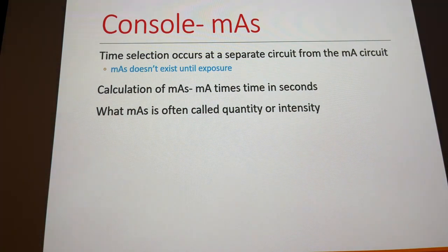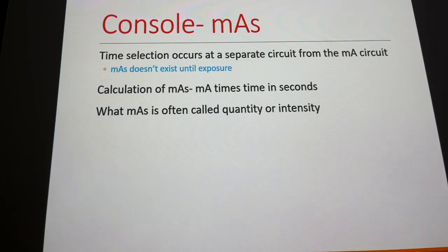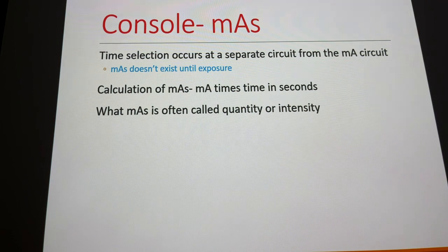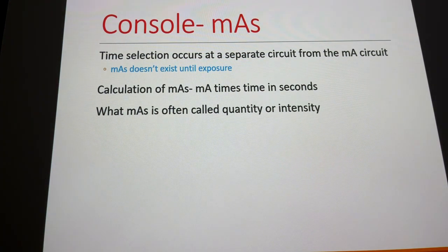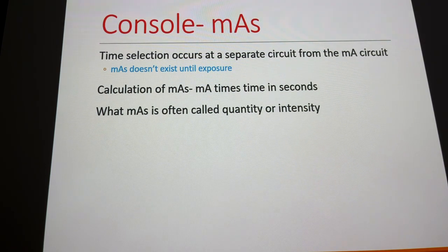Time selection occurs in a separate circuit, between the step-up transformer and the auto transformer. MAS doesn't exist until exposure. The calculation of MAS is simply MA times time in seconds. What we often call MAS is intensity — not in the sense of power, but just raw numbers of photons.